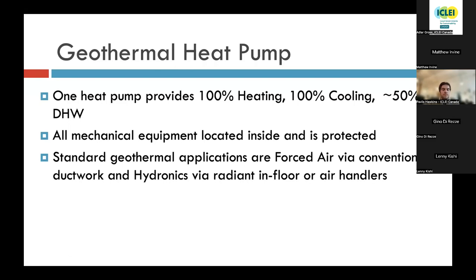You will get some hot water contribution in the cooling season in the summer, just not as much because we don't spend as much time air conditioning in the summer as we do heating in the winter. And then in the spring and the fall, you'll typically get a pretty marginal contribution because you're not doing a whole lot of heating or cooling. But it's seasonally biased, but annually it would be about a 50% contribution. And then all mechanical equipment is located inside and is protected from the elements and vandalism and rodents in the neighborhood or dogs, whatever you have going on. And then standard geothermal applications are forced air using conventional ductwork or, again, hydronics with radiant in-floor or potentially hydronic air handlers. Next slide, please.